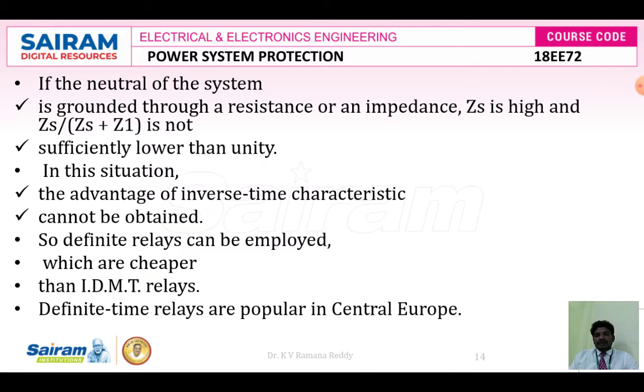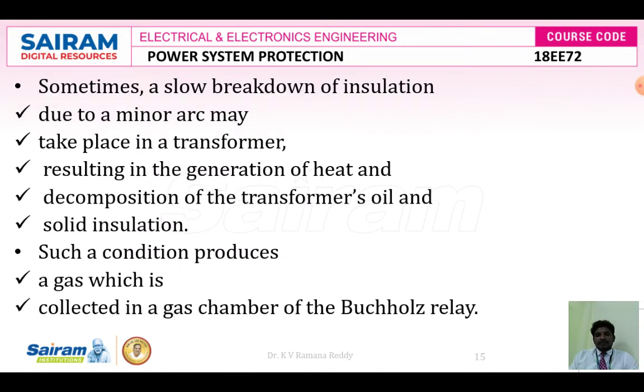In this situation, the advantage of inverse-time characteristics cannot be obtained, so definite time relays can be employed, which are cheaper than IDMT relays. Definite time relays are popular in Central Europe because they work based upon the time delay.